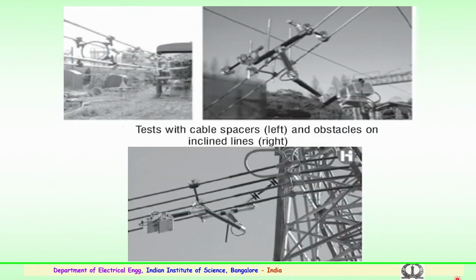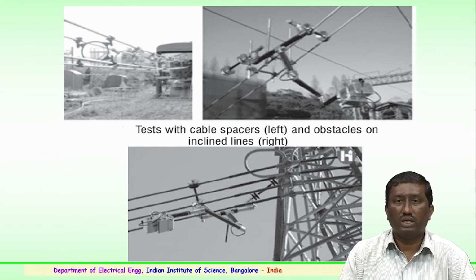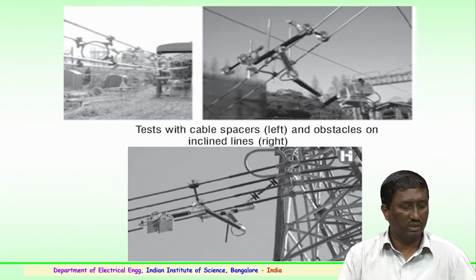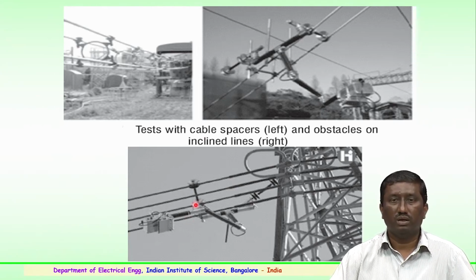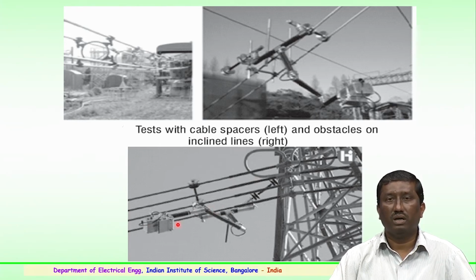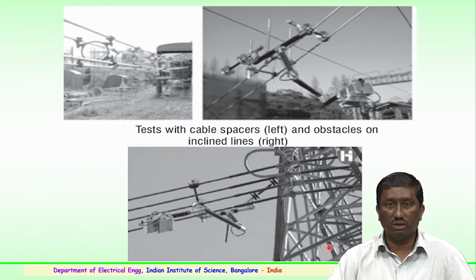So the tests with cable spacers and obstacles in the lines are being rectified using these various gadgets which have been developed for the overhead transmission lines. Some of them are shown here. From tower to tower, these gadgets will be moved and the information will be connected over the PC, and this information will be used to take proper corrections in case the conductors are damaged, or the spacer alignment is off, or mechanically the spacer is to be removed or replaced, or the conductors have to be properly checked. So this will be very helpful.